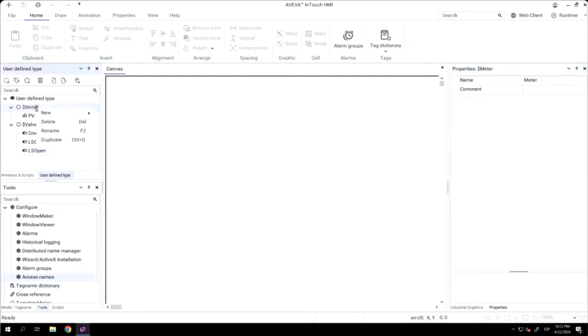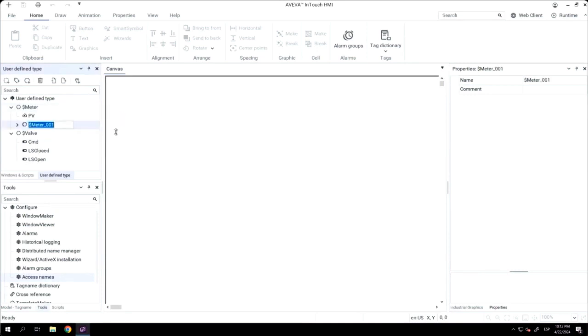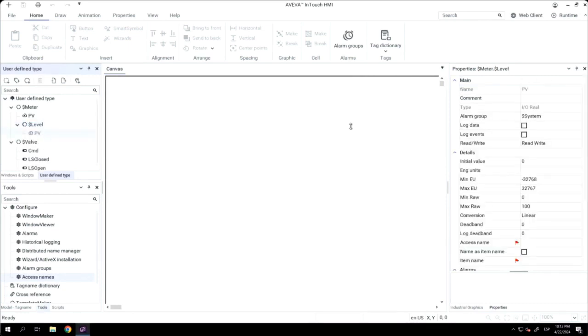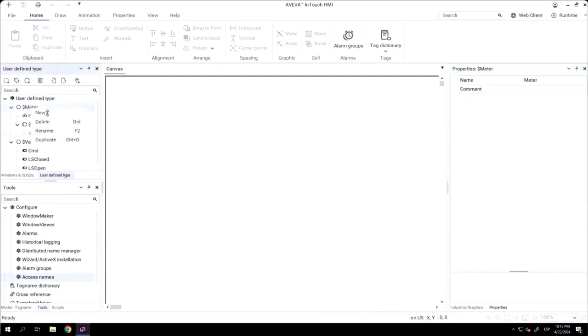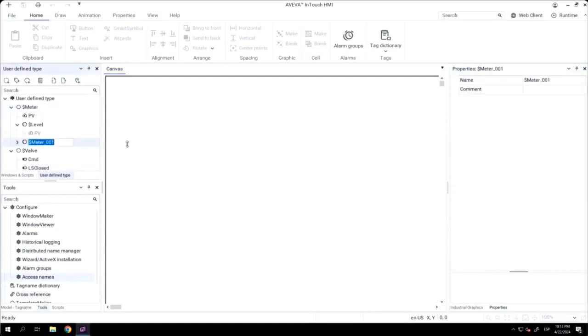The next step, I will create a derivative user data type. So, using the template of meter, I will create a level meter, and I will create a temperature meter. Now, I will change the engineering units for this level meter, and also, I'm modifying the minimum and maximum engineering units. I will do the same with the temperature meter.